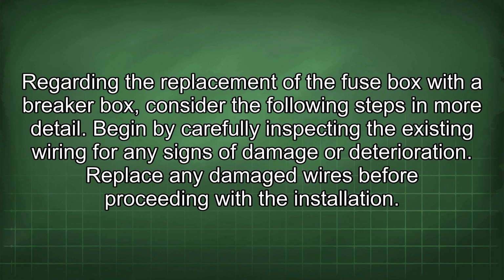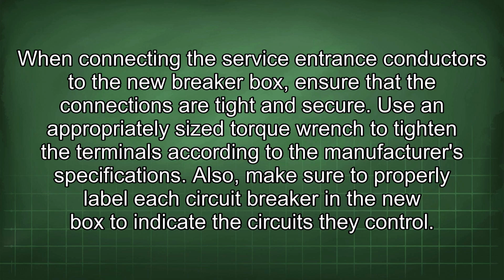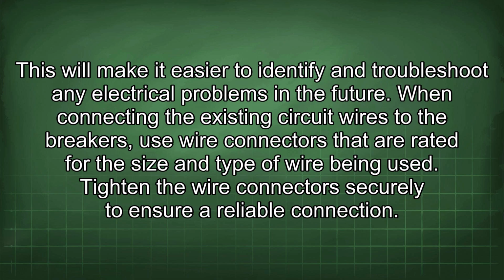Regarding the replacement of the fuse box with a breaker box, consider the following steps in more detail. Begin by carefully inspecting the existing wiring for any signs of damage or deterioration. Replace any damaged wires before proceeding with the installation. When connecting the service entrance conductors to the new breaker box, ensure that the connections are tight and secure. Use an appropriately sized torque wrench to tighten the terminals according to the manufacturer's specifications. Also, make sure to properly label each circuit breaker in the new box to indicate the circuits they control. This will make it easier to identify and troubleshoot any electrical problems in the future.